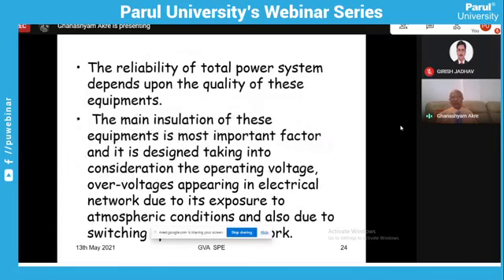Suppose you have got 66 kV, then the insulation between primary and secondary has to be 66 kV. That is for operating voltage, 66 kV phase to phase, and primary to earth will be 66 divided by root 3. So 38.1 kV is its continuously operating voltage, plus minus 10%. But it is tested at 140 kV for 1 minute.